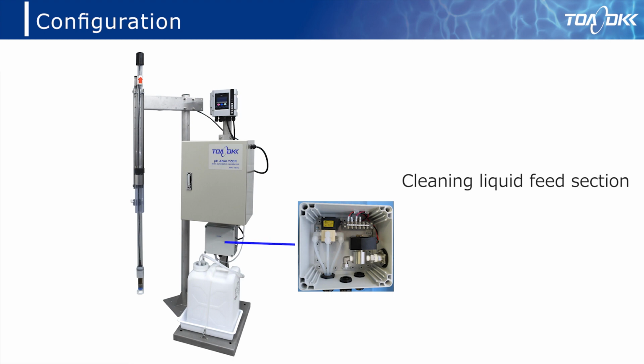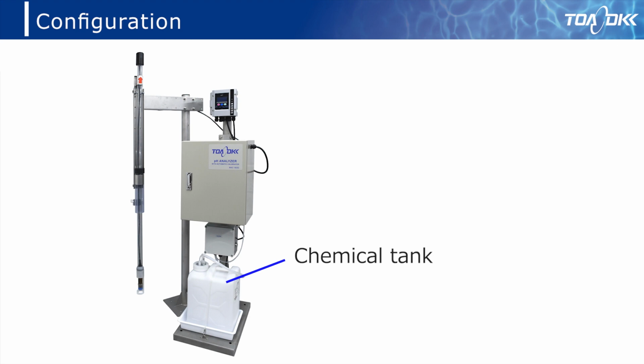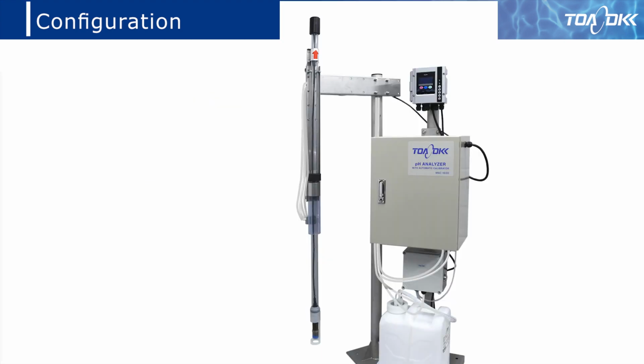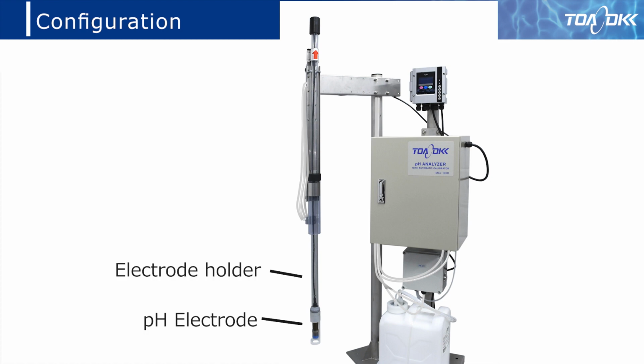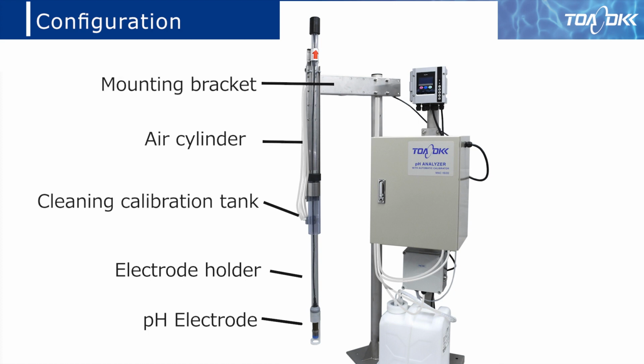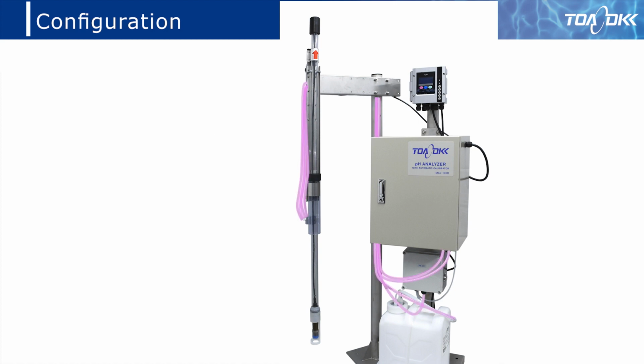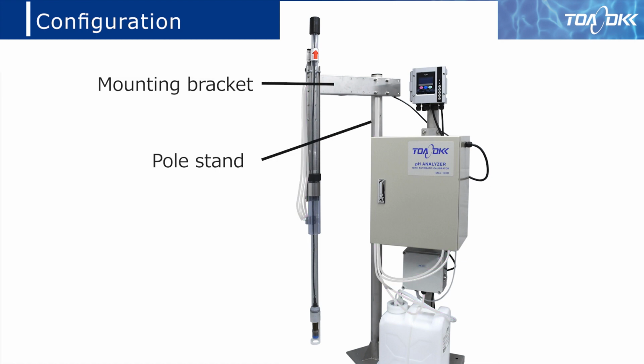The cleaning liquid feed unit controls washing water or tap water. Fill this chemical tank with the chemical solution. Please use 5% hydrochloric acid. The lift-up detector consists of pH electrode, electrode holder, cleaning calibration tank, air cylinder and mounting bracket. The main unit and the cleaning calibration tank are connected by various tubes. This is attached to the pole stand, but there are various other detectors which can be attached in a different method.